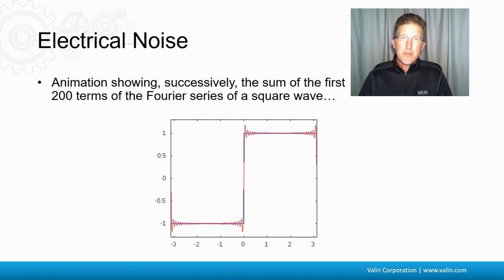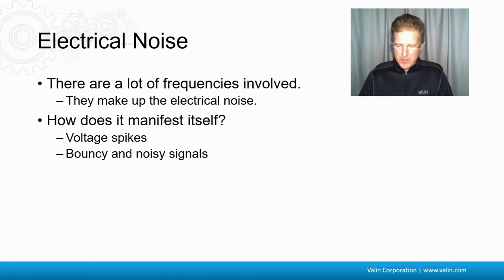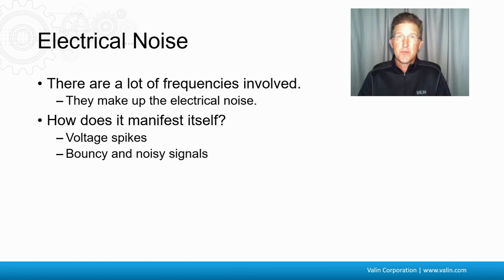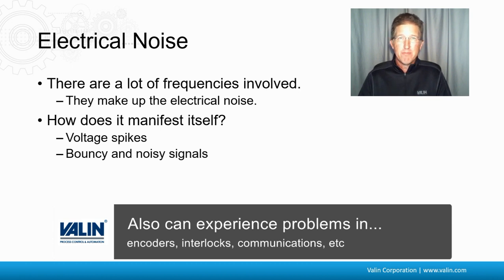That's why we end up with all these different frequencies. Those different frequencies manifest themselves in different ways — could be voltage spikes, could be noisy and bouncy IO signals. The most common one is that people will see sensors that are behaving erratically. They'll get false triggers, false positives, and think they have a bad sensor. But it very easily could be electrical noise, and it's pretty easy to solve just by installing the system correctly.